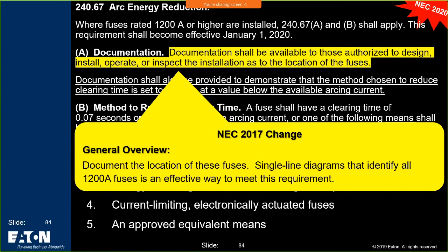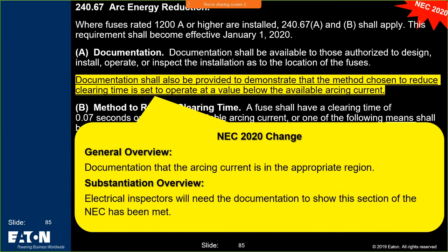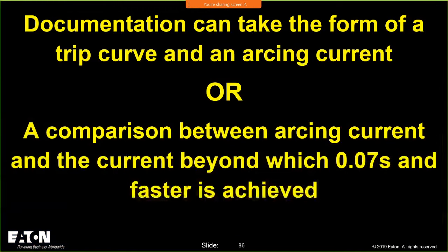All right, so you have to document it. Single line diagrams shall identify all the 1200 amp fuses. All you have to do is identify where you have these 1200 amp fuses. And then this is new for 2020. You have to document and show that your method to reduce will clear at the lowest arcing current. I throw in the word lowest. Probably a good suggested change.